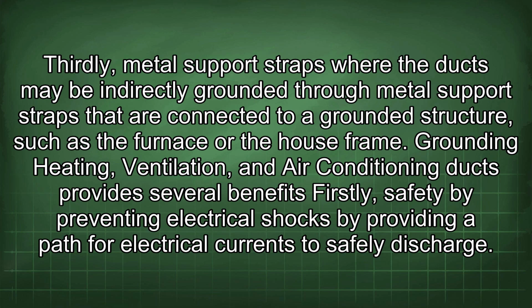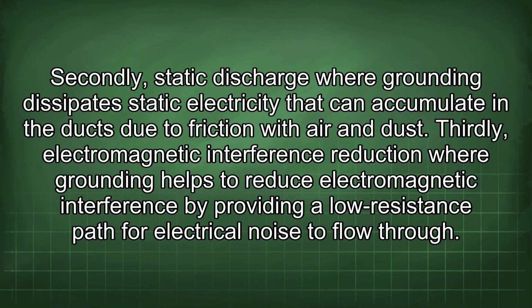Grounding heating, ventilation, and air conditioning ducts provides several benefits. Firstly, safety by preventing electrical shocks by providing a path for electrical currents to safely discharge. Secondly, static discharge, where grounding dissipates static electricity that can accumulate in the ducts due to friction with air and dust. Thirdly, electromagnetic interference reduction, where grounding helps to reduce electromagnetic interference by providing a low resistance path for electrical noise to flow through.